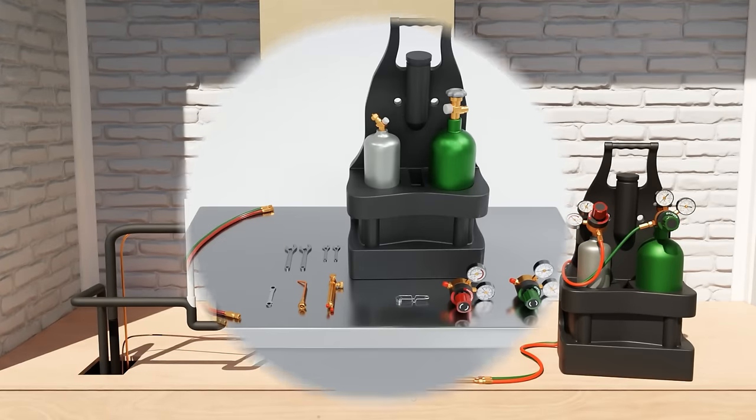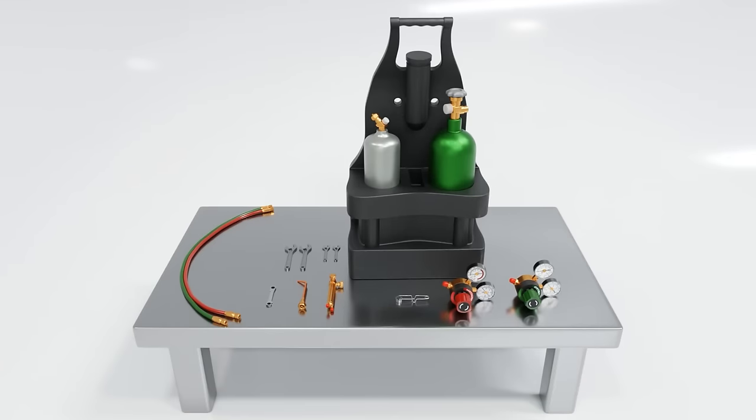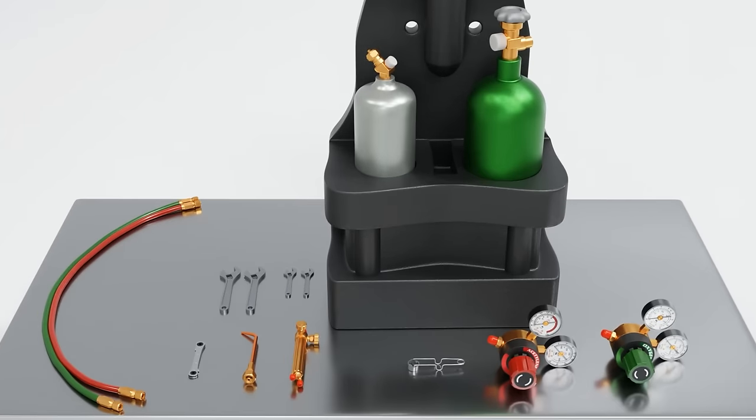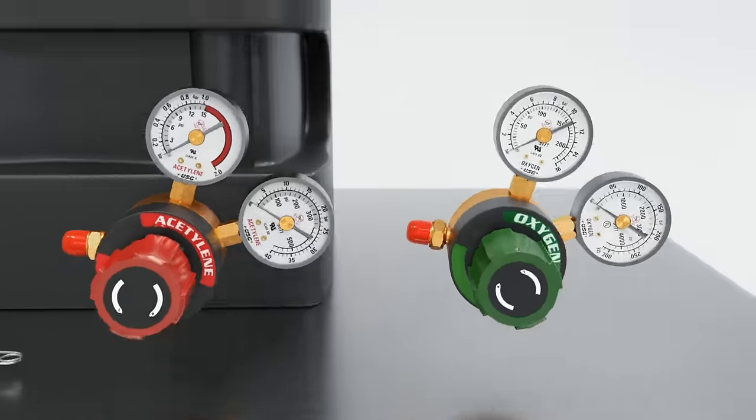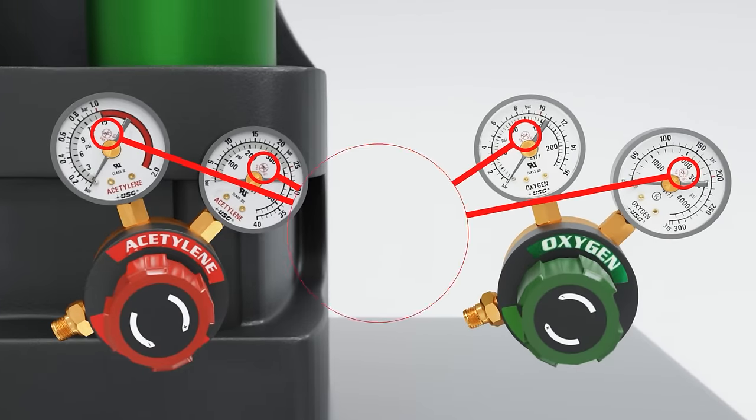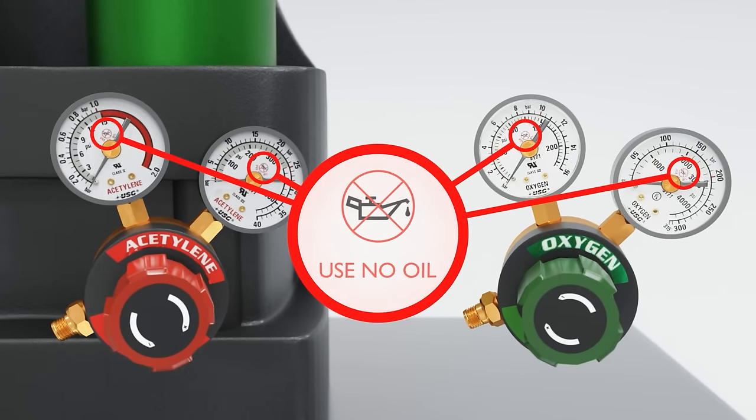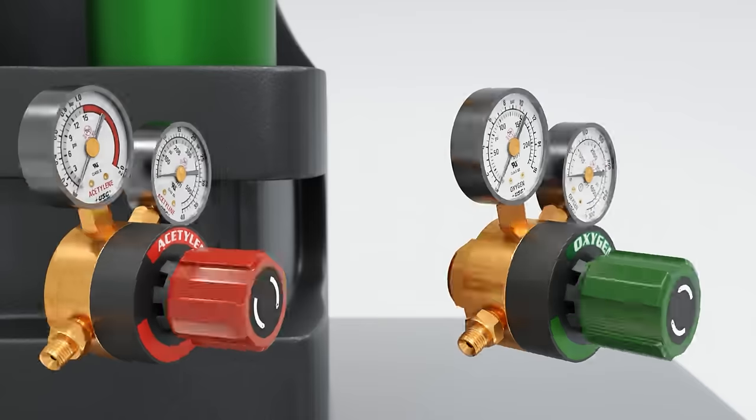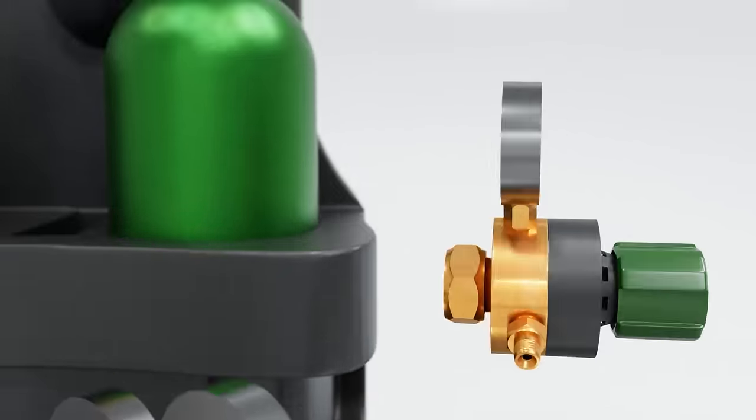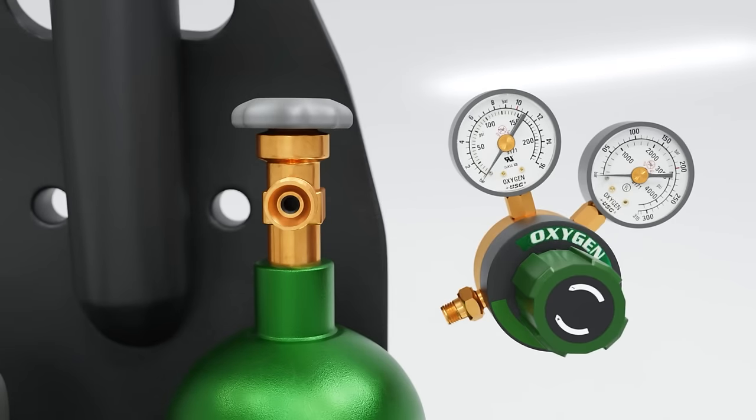Next, we're going to show the proper setup of an oxygen and acetylene torch rig. First, keep in mind that you're not supposed to use oil on the threaded connections of your regulators. This is especially true on the oxygen side, as oil or lubricant on the oxygen threads can result in combustion, unless it's specifically designed for that purpose.